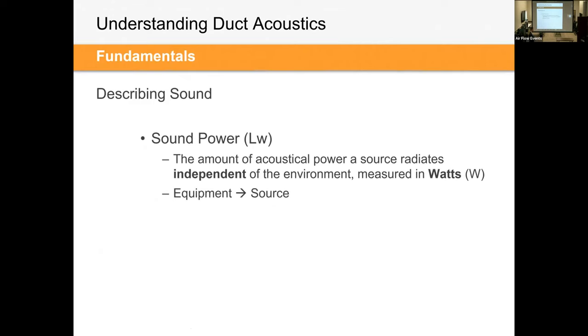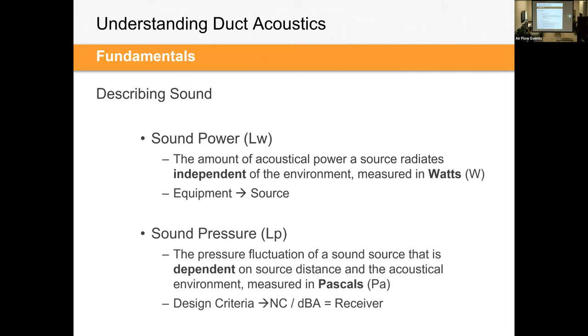There's an important difference between sound power and sound pressure. Sound power, denoted LW, is the amount of acoustical energy independent of environment — it stays the same regardless of where the device is located. Sound pressure, denoted LP, is very dependent on environment: where you're located, how far away you are, and whether you're indoors or outdoors.